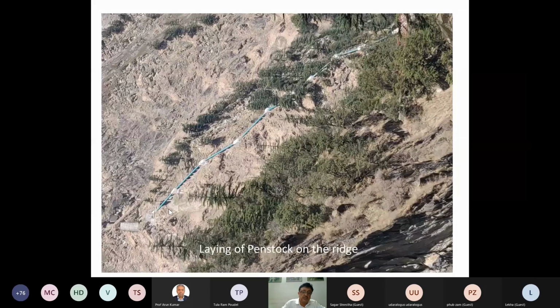It should also be ensured that during erection of the penstock, conduit or cable tray shall be laid along the penstock up to the surge shaft during penstock erection only, as cables are to be laid for penstock protection, lighting, and signal cables for the water level sensor.